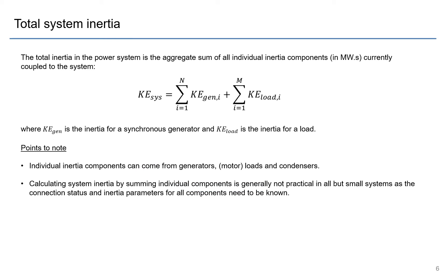So far we've talked about inertia purely from a single generating unit perspective, but probably what's more interesting for us is what is the total inertia in the power system. And this can be calculated as the aggregate sum of all the different inertial components that's currently connected to the system, and in general theoretically this is the sum of all synchronous generators in the system as well as all the synchronous loads in the system. So inertial components can come from synchronous generators, synchronous motor loads, as well as synchronous condensers.